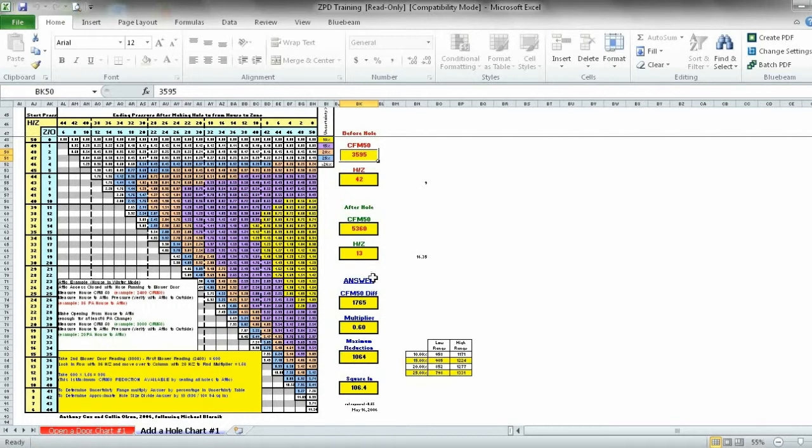And another important aspect of this that's critical: if we're taking time to take these measurements, we want accurate measurements. So if we can get in this gold zone, we can have about a 10% uncertainty. Purple is 15, brown is 20. Anything 20 or beyond probably is not going to be worth taking the number. So we want to start out in this zone. We started out at 42 and we moved all the way across to 13. So we're solidly in this purple zone. So we've got pretty accurate numbers.